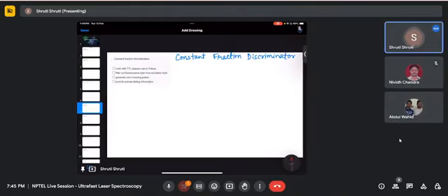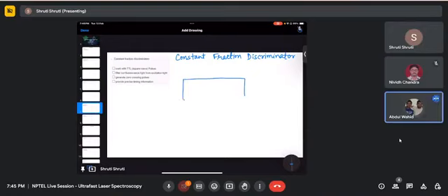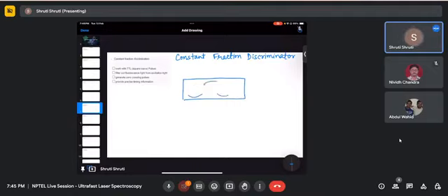because as you said, when you excite the sample, it is a pulsed laser, and a lot of photons will get generated. But that may saturate the detector, because we are doing this experiment millions of times, at least thousands of times it will take to generate one lifetime decay. So if that many photons are coming continuously, it will saturate the detector and it will not give any signal after that.